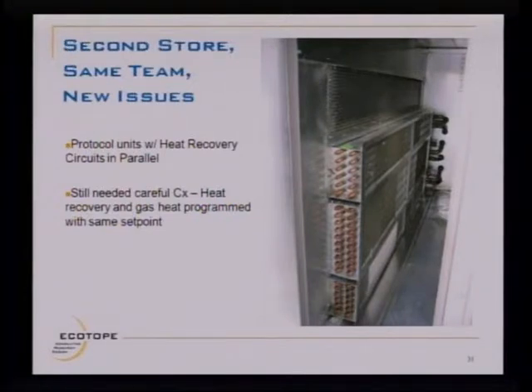The set points for the heat recovery and the gas heat initially were the same set point. So we're just trying to keep the store at 72 degrees. First stage heating is the heat recovery. Second stage is natural gas. Well, there'd be a call for heat from the thermostat. It would let the refrigerant go to the heat recovery coil. Two minutes later, the thermostat's not satisfied, so the natural gas comes on. It heats the store up to 72 degrees. There's no more call for heat, and so the gas turns off and the heat recovery turns off until the store drops down again.